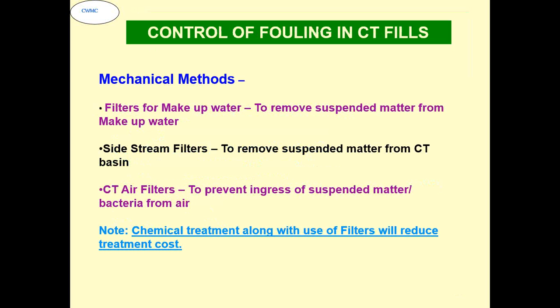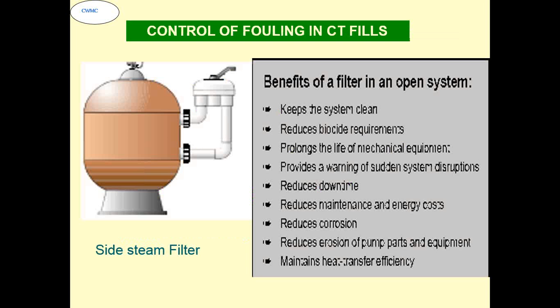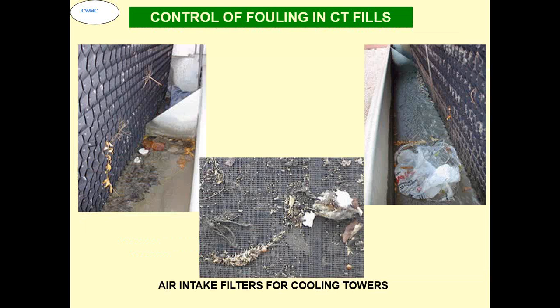For fouling, in CT fills, cooling tower fills, PVC fills, the mechanical methods are filters for makeup water, side stream filters to remove suspended solids from the CT basin, and CT air filters to prevent ingress of suspended matter. Chemical treatment along with the use of filters will reduce treatment cost. This is a typical side stream filter. This is a typical air filter for the cooling tower, but normally in our places it will become too expensive, so people will not go for this.